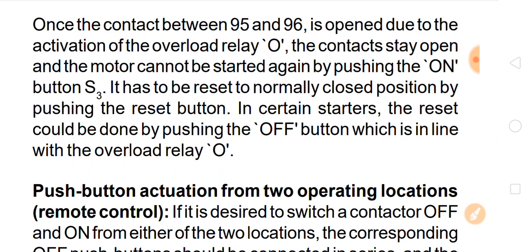Once the contact between 95 and 96 is open due to activation of the overload relay, the contact stands open and the motor cannot be started again by pushing the on button S3. It has to be reset to the normally closed position by pushing the reset button. In certain starters, the reset could be done by pushing the off button which is in line with the overload relay.